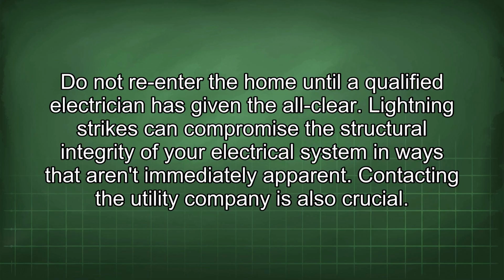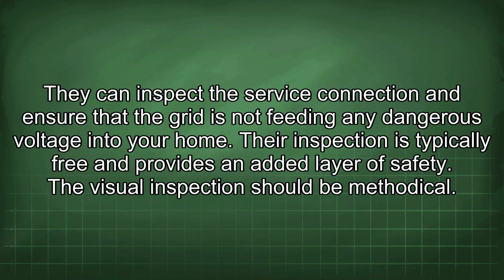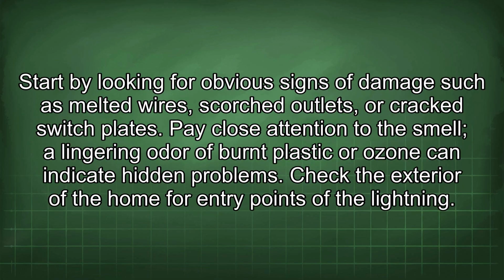Contacting the utility company is also crucial. They can inspect the service connection and ensure that the grid is not feeding any dangerous voltage into your home. Their inspection is typically free and provides an added layer of safety. The visual inspection should be methodical. Start by looking for obvious signs of damage such as melted wires, scorched outlets, or cracked switch plates. Pay close attention to the smell. A lingering odor of burnt plastic or ozone can indicate hidden problems.